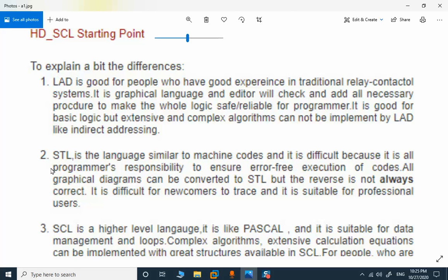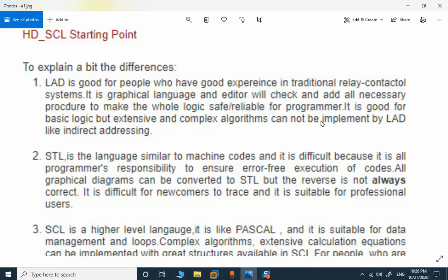You need to get the status word of the PLC and check it for a specific flag, whether this flag is active or not. If it's active, you need to jump and develop your fault behavior there. But all this fault detection is performed automatically in ladder.